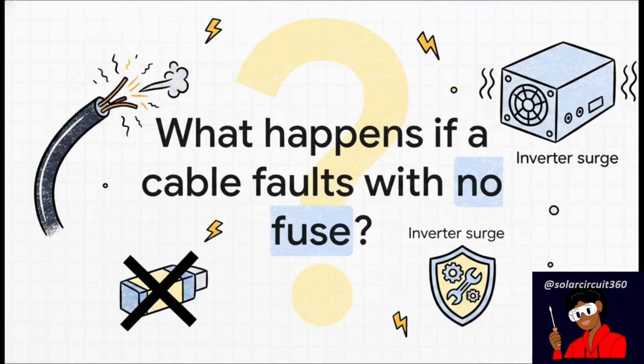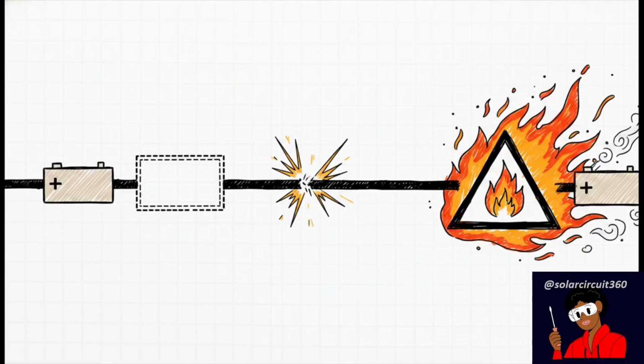I want you to ask yourself this. What actually happens if a cable faults and you don't have a main fuse installed? Imagine you get an unexpected inverter surge, or maybe a damaged cable housing is rubbing against a sharp metal edge. Just pause for a second and really think about the consequences of all that raw energy suddenly having nowhere safe to go. Well, the reality is pretty stark. A battery this powerful doesn't just politely stop pushing energy when a cable breaks. Oh no, it'll immediately dump all 4.8 kilowatt hours right into that short circuit. Without a properly sized primary fuse acting as a physical breakpoint, that shorted or undersized cable turns into a glowing red heating element in seconds. Basically, an unfused cable fault transforms your carefully crafted energy storage system into a severe, completely uncontrollable fire hazard.